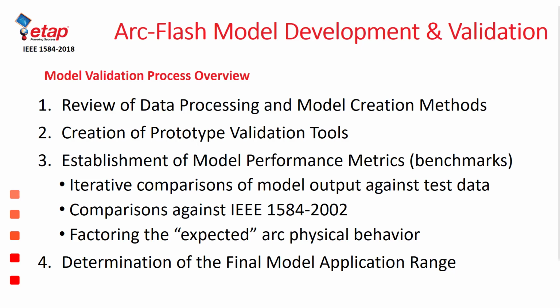Another phase of the validation process was the establishment of the model performance metrics, otherwise called benchmarks. The benchmarks included iterative comparisons of the model output against the actual test results. The model validation process also included comparisons against the 1584-2002 model. And of course, as I mentioned already, the factoring of the expected arc physical behavior was also added into the mix in this model development.